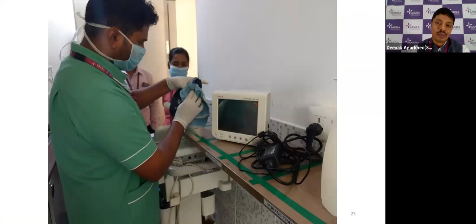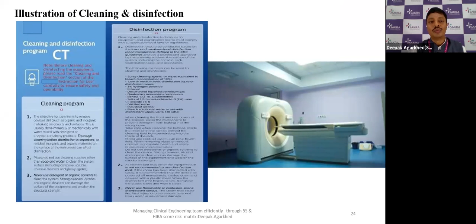So this is the way in which cleaning followed by disinfection is happening with the sodium hypochlorite solution in our hospital. As I was mentioning, cleaning and disinfection is not restricted to one sort of equipment. For all the equipment, cleaning and disinfection has to be done. So you need to get the protocol of cleaning and disinfection from the service providers, very, very important, and follow the norms. If you do something which has not been prescribed by them, it may void the warranty or the contract. So please ensure that cleaning and disinfection is followed in totality based on the OEM's norms.